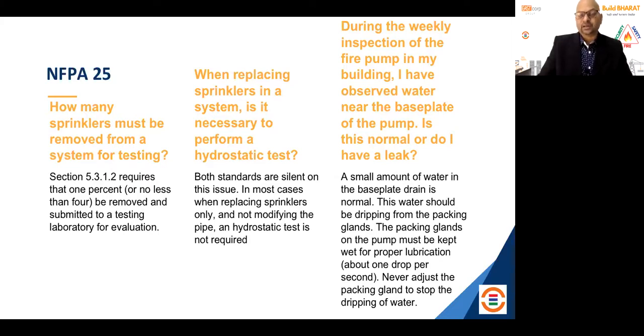Suppose you have 400 upright sprinklers, you take 4 sprinklers out and test them. If you have 500 pendant sprinklers, you take 5 out and send them to a third-party laboratory for testing. If one fails out of 4, or one fails out of 5, you replace all 400. Simple, clear. But that is what NFPA 25 says.